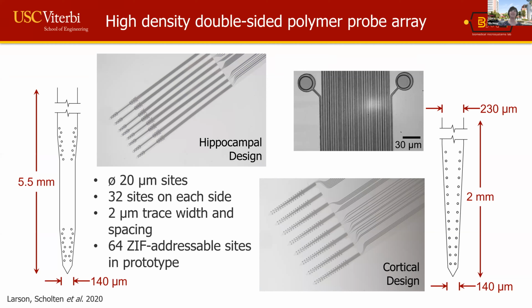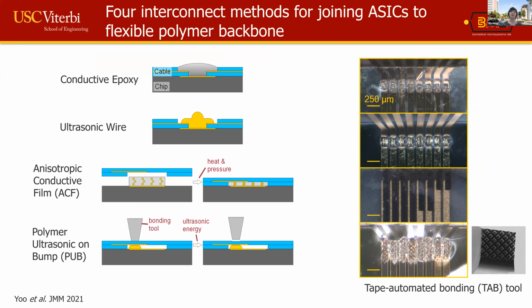Now, we are still limited, until the application-specific integrated circuits are developed, to conventional connectors. And so you'll see on the back end, the wiring out is not very dense. That's because we're just using standard 64-channel connectors to address a subset of the electrodes in our current devices to do some initial testing. In order to get the electronics on the back end, we looked at many different approaches all at the same time. And these are the approaches that we looked at. We looked at using conductive epoxy, making rivet bonds using ultrasonic wire bonding, purchasing anisotropic conductive film, and establishing many connections all at once using heat and pressure.